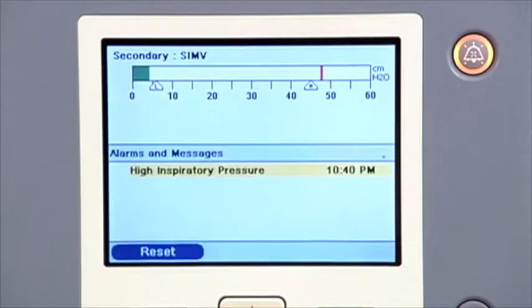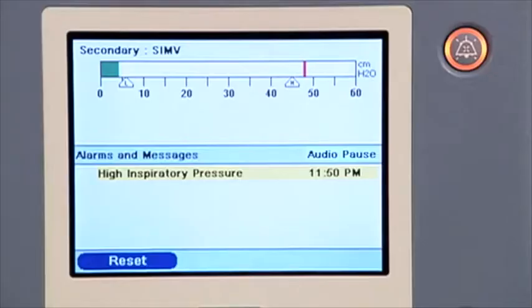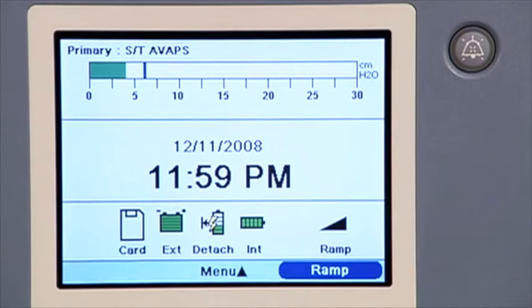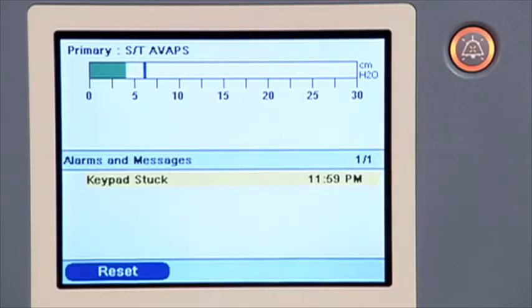This is a medium priority alarm. You hear 3 beeps in a repeating pattern, and the audio pause button flashes yellow. Medium priority alarms require prompt attention. An alarm message will appear on the display screen. Medium priority messages appear highlighted in yellow. Trilogy 100 also has a number of low priority alarms, which convey information that you should be aware of. For example, a button is stuck, or the detachable battery needs to be charged. Low priority alarms are two beeps together in a repeating pattern. The audio pause button shows a solid yellow light. The alarm message is highlighted in yellow.